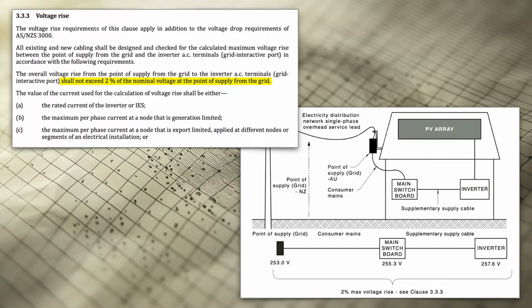Certainly in Australia, our lines companies, our DNSPs often have a standard online application form, and you have to put in the size of your inverter supply cable, your submain, and your incoming consumer mains separate from the submain to the inverter, and so you may have 1% on either side. I think in New South Wales there's even Essential Energy, I think, have 3 sections that you have to meet the requirement for. So yeah, this is all about the reliability of the supply voltage, keeping it within certain bounds.